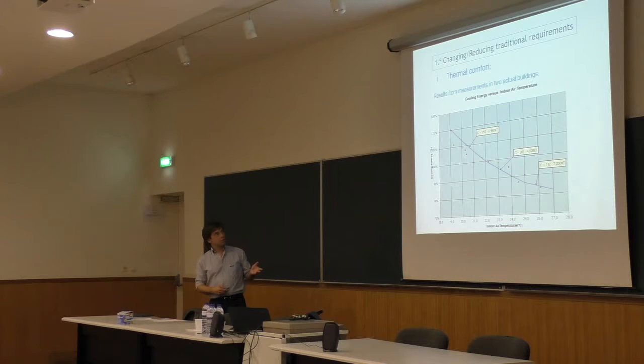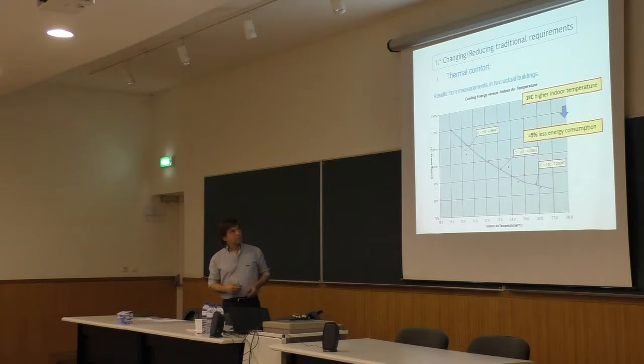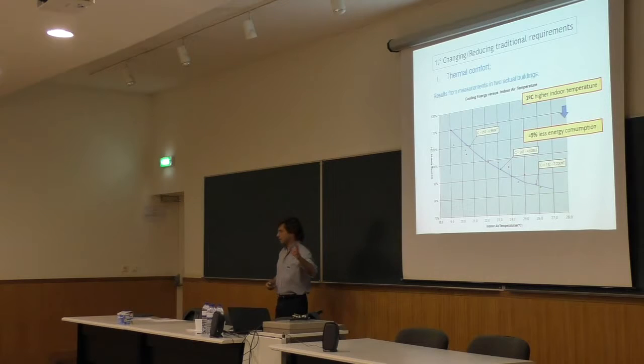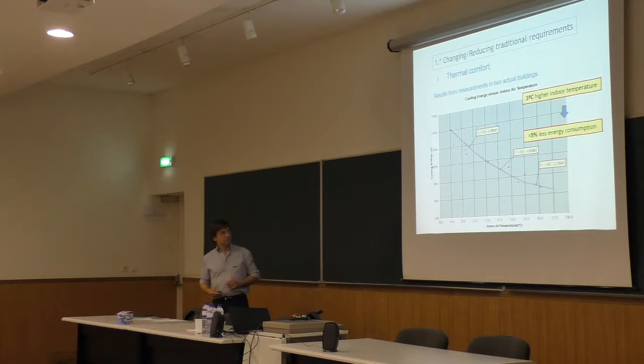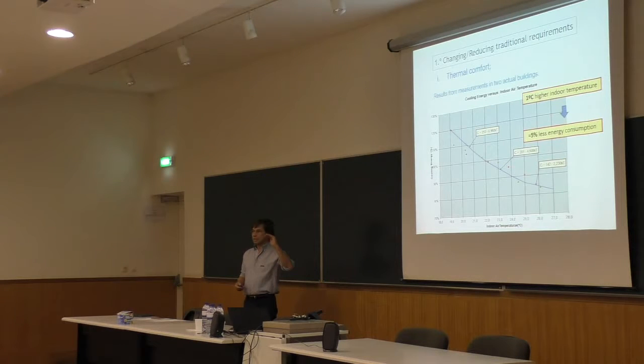What this chart shows is that, on average, each degree Celsius increase in indoor air temperature implies a 5% decrease in energy consumption of the air conditioning system. This was measured by me and agrees with many published articles on the issue. So it's very important to have the highest temperatures possible indoors in summer, and the lowest possible within the comfort range in winter.